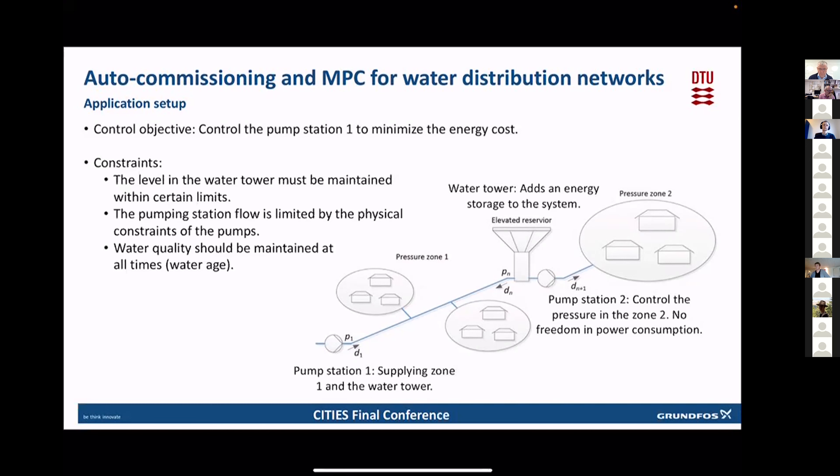The system we are considering is like this, where we have a pumping station feeding a lower pressure zone — pressure zone one — and feeding a water tower, which is our storage. And then we have a second pressure zone fed by a second pump. If we change anything in this second pump station, it would immediately change the conditions in the pressure zone, meaning we have no freedom to change any operating condition in that pump, meaning it cannot be used for supporting the electrical grid. Whereas the other one is supplying both the pressure zone and the water tower, which is really our storage. So here we have some freedom.